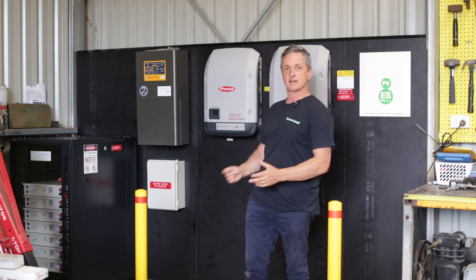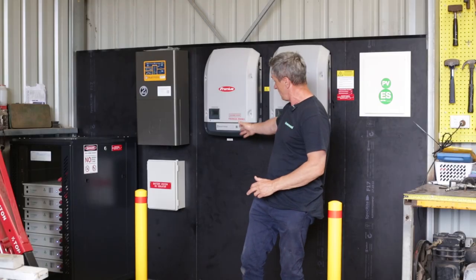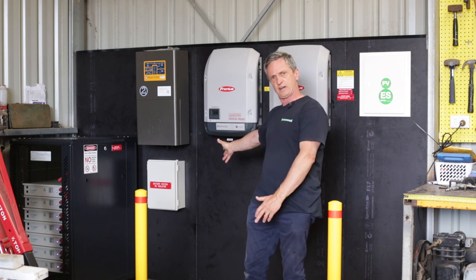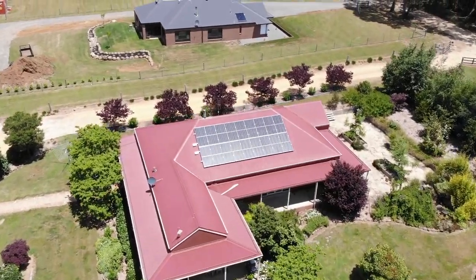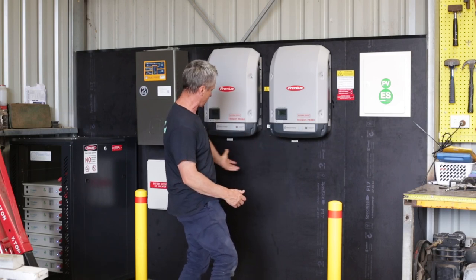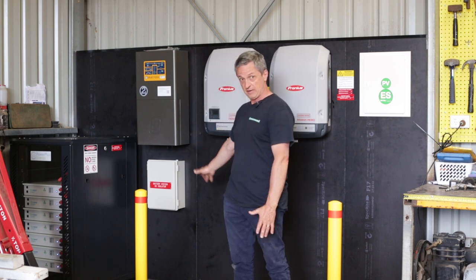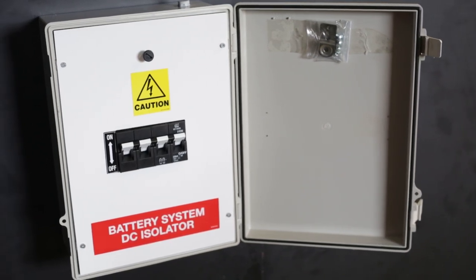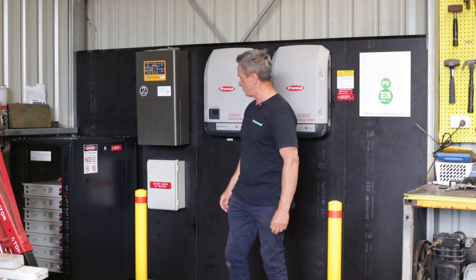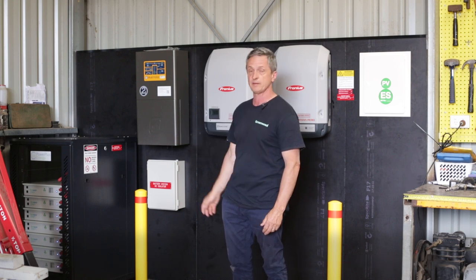You may notice that there's no cables — we've gone for that particular aesthetic. Very clean. There's no DC isolator here because the Fronius Primo has a built-in DC isolator that works in conjunction with the DC isolator on the shed roof and on the house roof. The inverter charger must be isolated from the batteries, so we have a 250-amp DC isolator that is housed in this enclosure here, and a very short run of 70mm square multi-strand cable that goes to the DC bus bar in the back of the Power Plus cabinet.